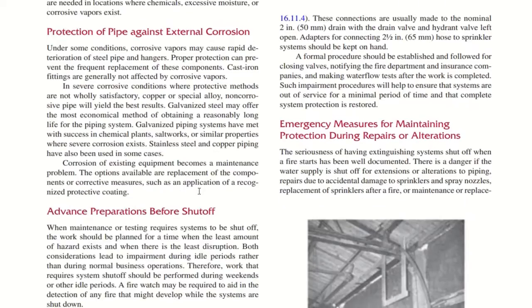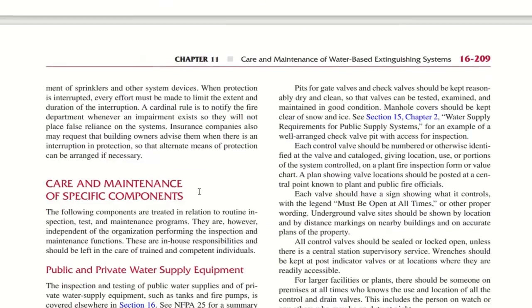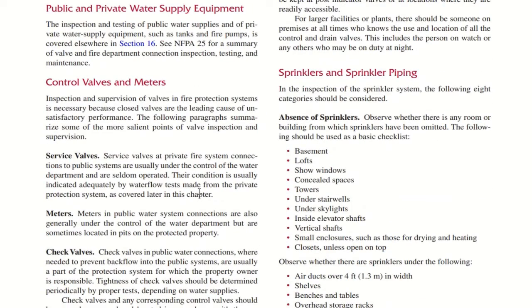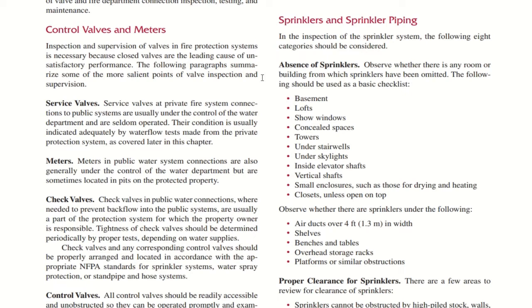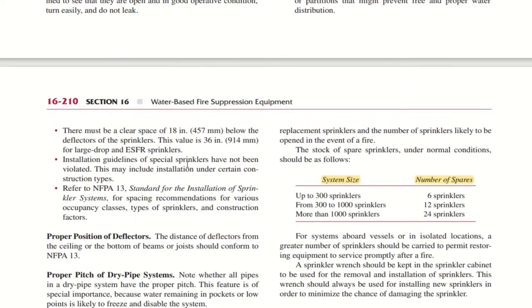Apart from that, since this covers the maintenance part, you can find all these topics here. So sprinklers and sprinkler piping, inspections, and so on. System size up to 300 sprinklers: the number of spare sprinklers you need to consider is shown here. 6 sprinklers up to 300 sprinklers. If the building has more than 300 sprinklers up to 1000 sprinklers, then the spare sprinklers shall be 12, and if it has more than 1000 sprinklers, the number of spare sprinklers shall be 24.